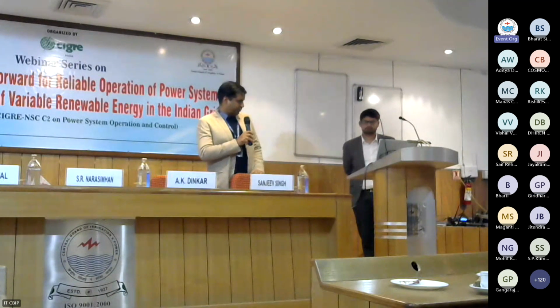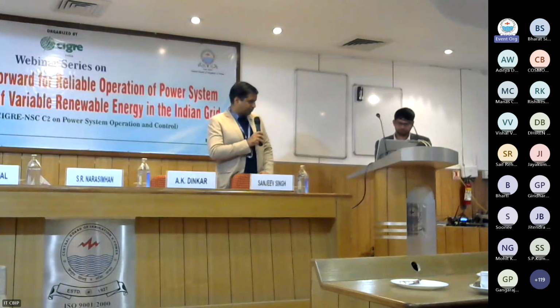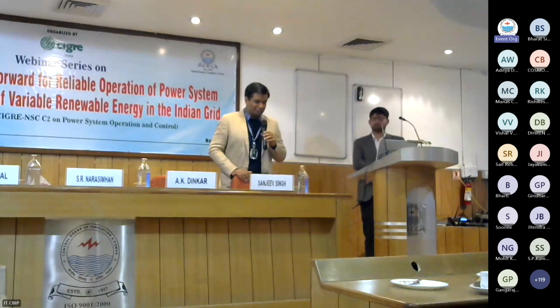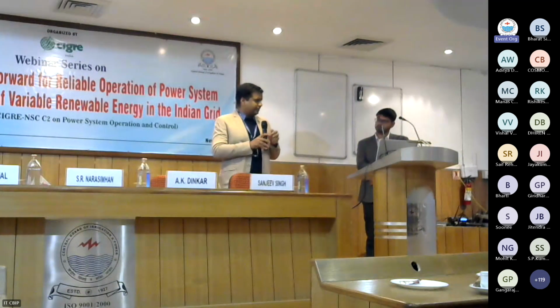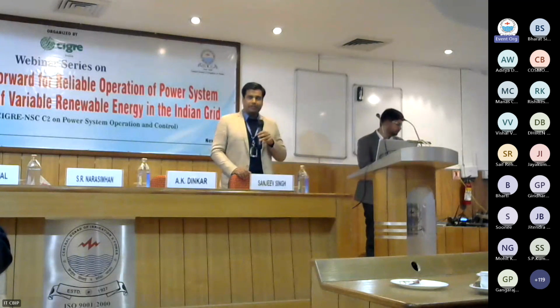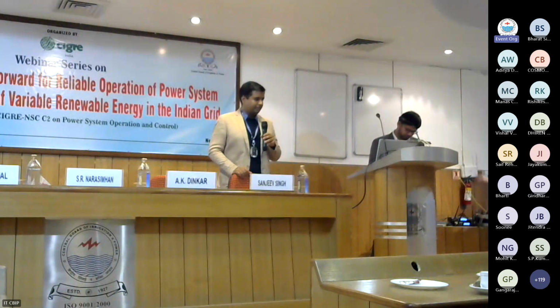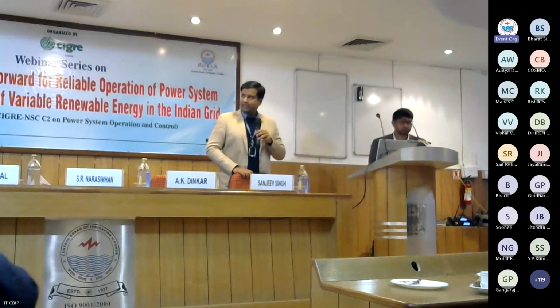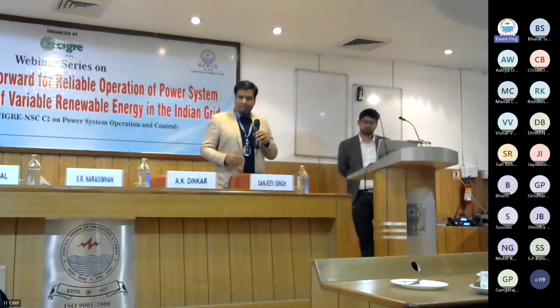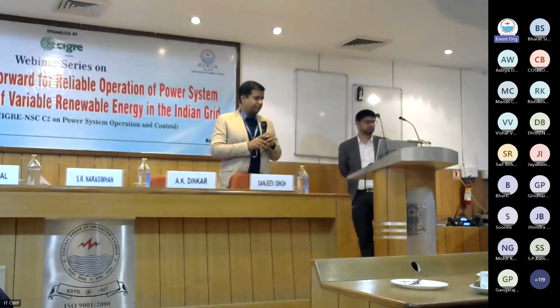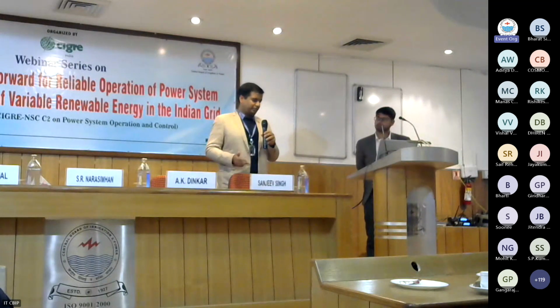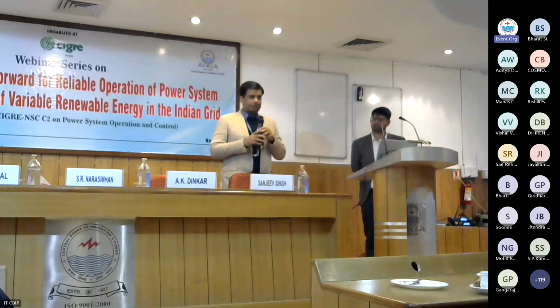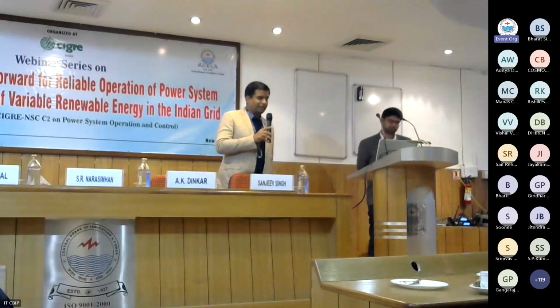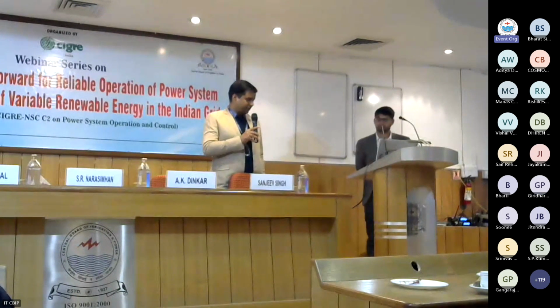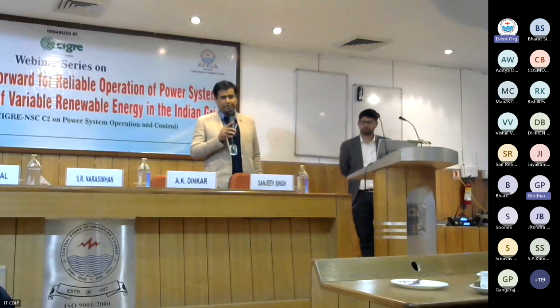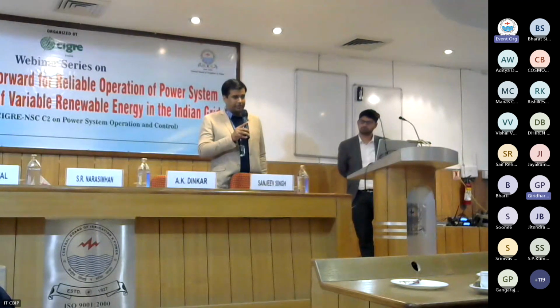So actually, we are from National Load Dispatch Center, which is under Grid Controller of India. We are grid controllers. We are adding that as our operational feedback. As of now, grid forming inverters are not available in the regulations, but we expect that they will be added, or will be under discussion, since we have discussed the requirement for the Indian grid in our report as well. So it all depends on the future, how things turn up. But yes, they are required, and for standards, you can refer to the UK grid code, where we have the requirements of grid forming inverters.